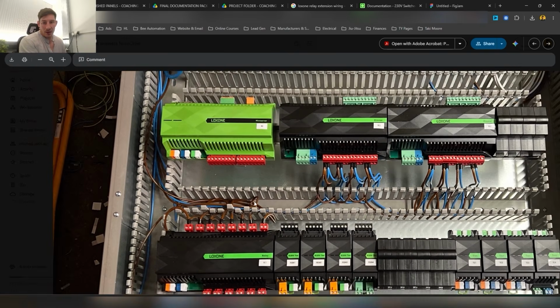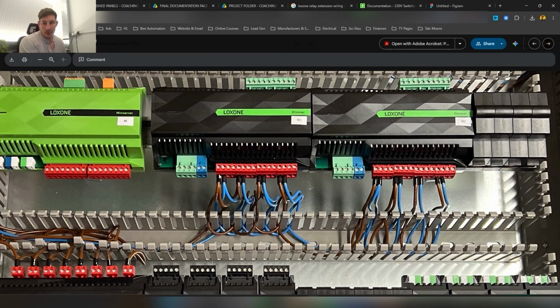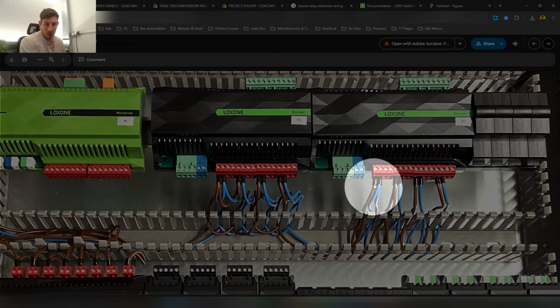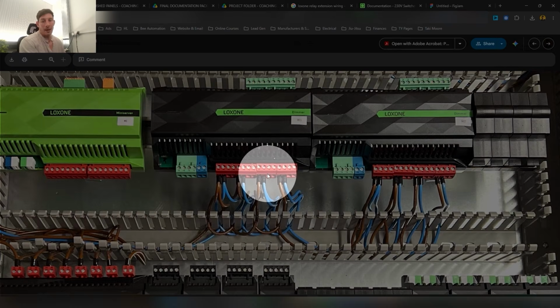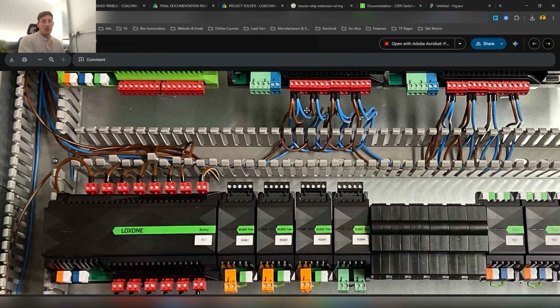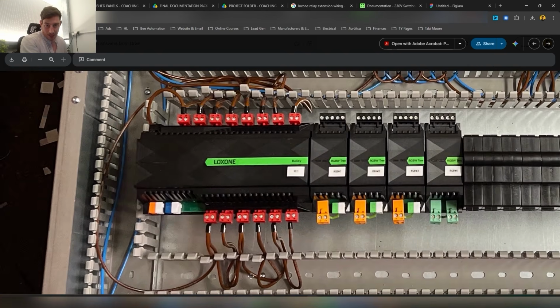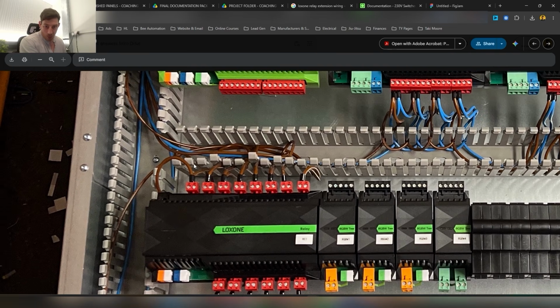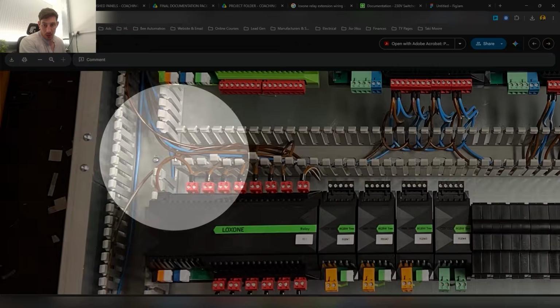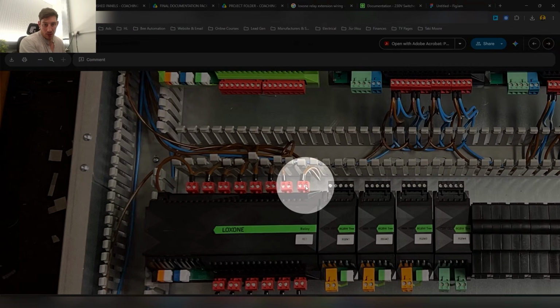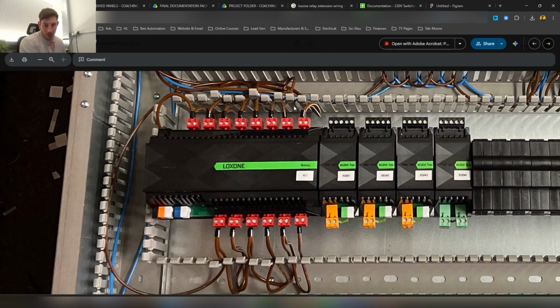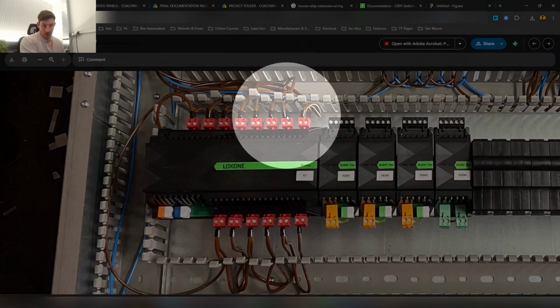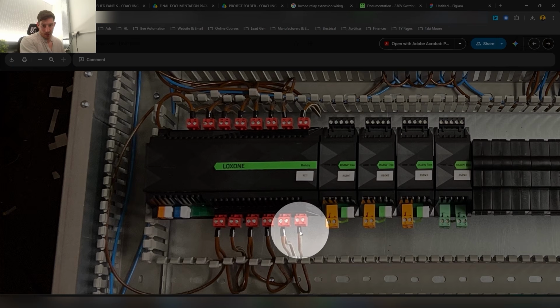But I've done, as you can see, the supplies for the dimmers - the supply live in, the neutral feed in, swooping, swooping, swooping, going over here, finishing off here. Later on you'll see the switch side of the dimmer going out down here to these terminal blocks, and it's a similar thing with the neutral, with the relay extension - we've got the feed coming in, swooping, swooping. There's 2 RCBOs being used on the relay extension - you can see there's the end of the line of one because it's only a single ferrule, and end of the line for the other.